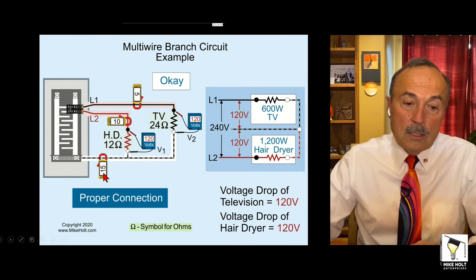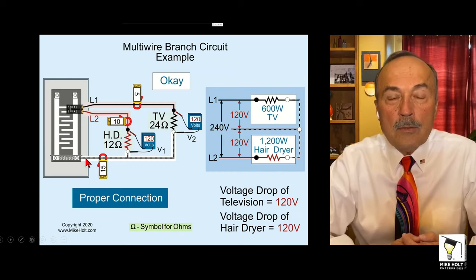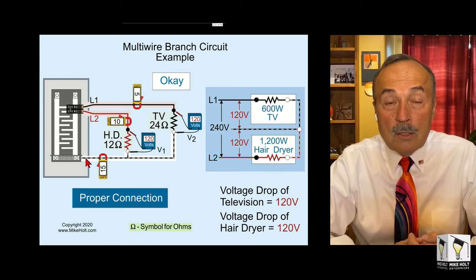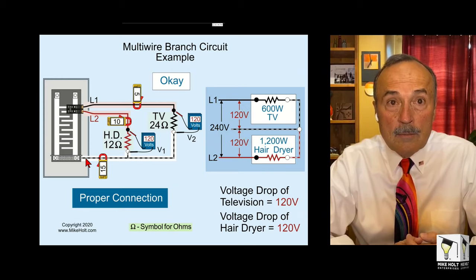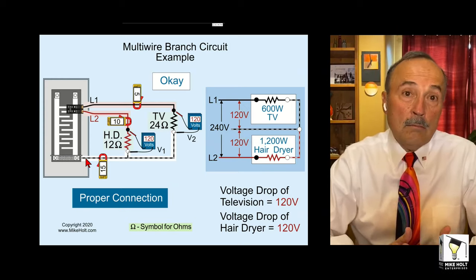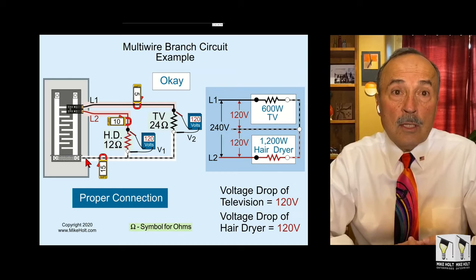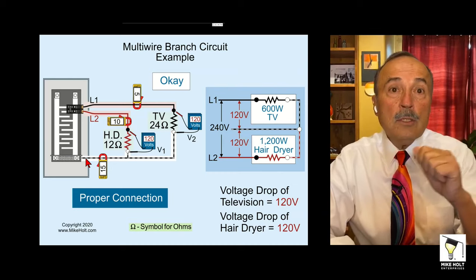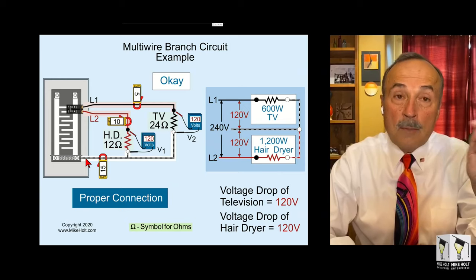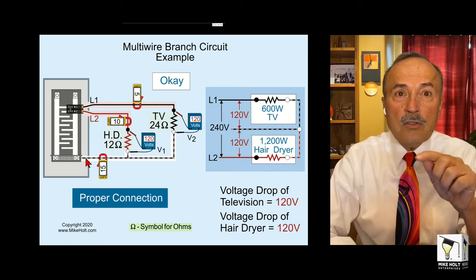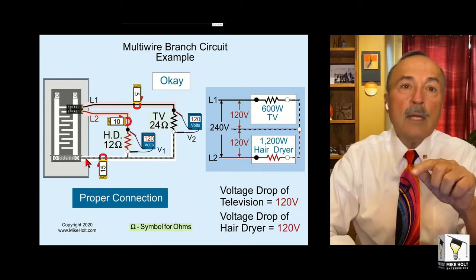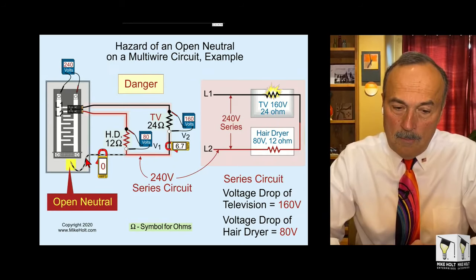What he could do is, unfortunately, sorry, that drives me nuts. He could put an amp meter on that neutral. If that neutral conductor is carrying current, well, then we know it's being shared by another circuit. Then start turning off your breakers to determine which breaker, and there might be more than one breaker, that's contributing to that neutral conductor. Then you're going to have to go in and troubleshoot the circuit.